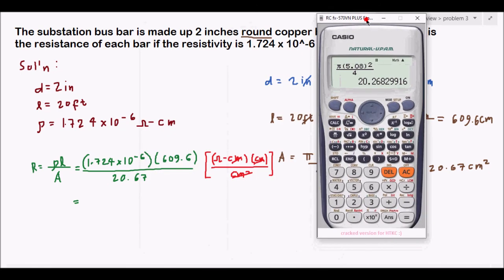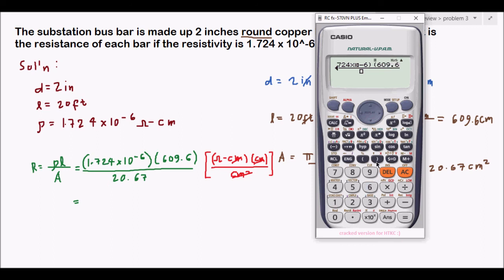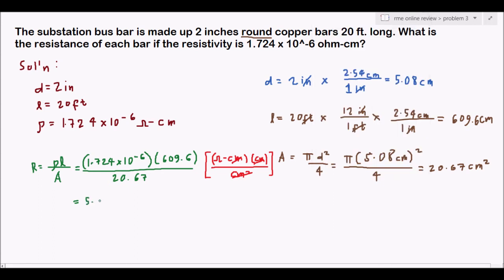Now substituting into R = ρL/A: R = (1.724 × 10⁻⁶ × 609.6) / 20.67. Using the calculator, the answer is 5.08 × 10⁻⁵ ohms. That is our final answer for the resistance of the bus bar.